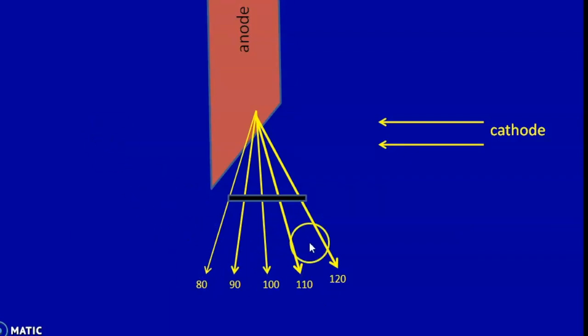Second is by altering the SID. SID is the source image receptor distance. We can reduce or increase the anode heel effect by altering this SID, also called as focal film distance. Notice when the film is close to the source, it is exposed to beams of both extreme ends, a wider range of beams and thereby the anode heel effect increases. But when the film distance increases, the diversity of exposure is less.